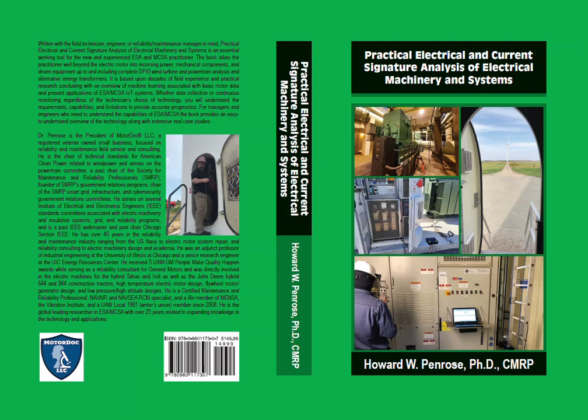He contacted me one day as they had a problem with a vertical 900 horsepower synchronous pump motor that had snapped a 24-inch diameter coupling. He brought me several printouts to the next section meeting a few days later, and one of the datasets was MCSA data. I noted a specific pattern around line frequency that looked like pole pass frequencies, a high one-time running speed sideband, and very high harmonics around line frequency peaks that could also be associated with dynamic eccentricity.